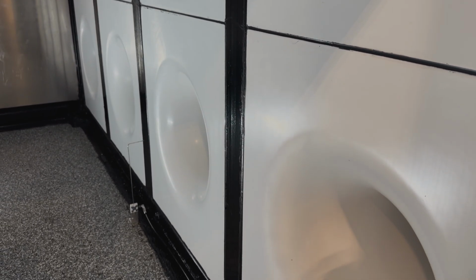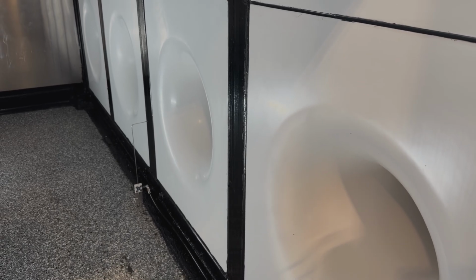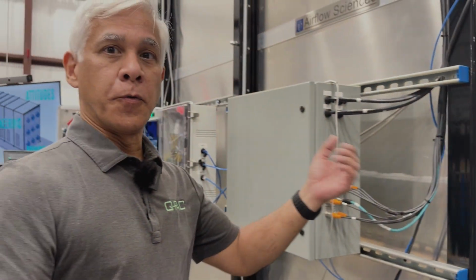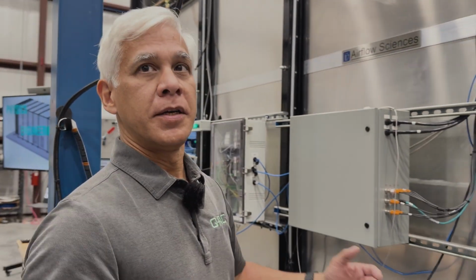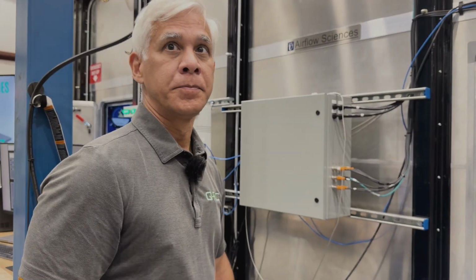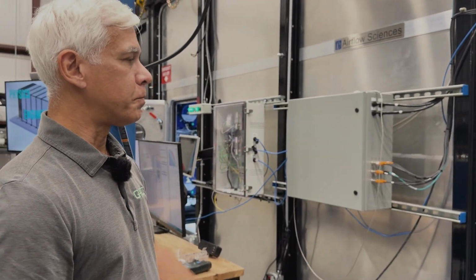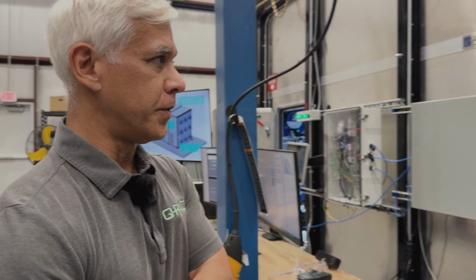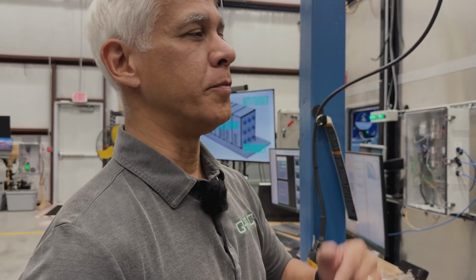So we don't actually measure air directly, we measure pressure between this wall and the wall we just looked at, or the room we just looked at. That pressure difference times the number of nozzles open, times the formula for that particular nozzle, tells us the airflow we have flowing through there. That's pretty cool. And so that's one of the three most important measurements we're doing, the amount of airflow. The second one I didn't mention when we were over there in that first section is the pressure, right?